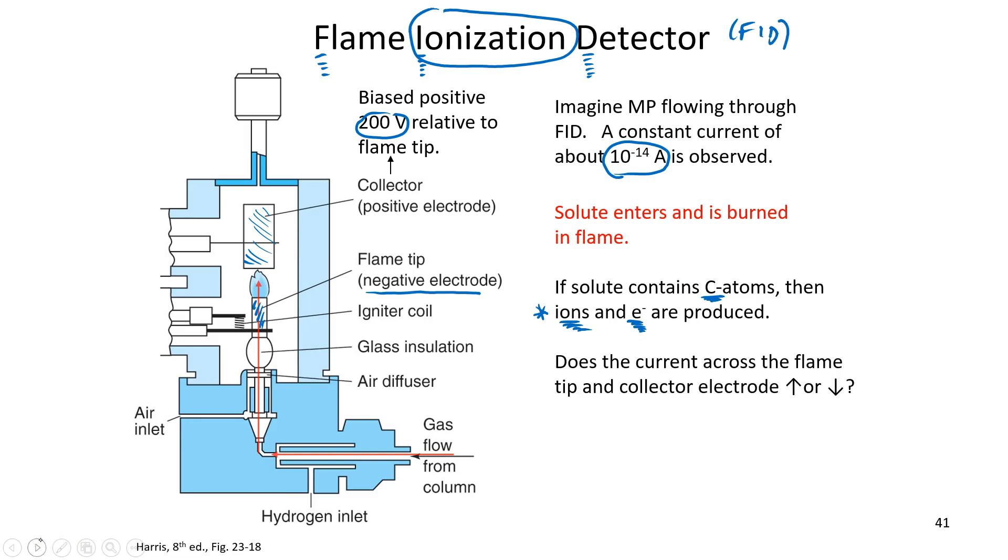Well, I bet you're thinking what I'm thinking. I bet you're thinking that the presence of these ions and electrons are going to increase that current. And that's right. So that's the response that we measure in the FID. Again, the solute comes in, it's burned, ions are produced, and there's an increased current across the flame tip and that collector electrode.